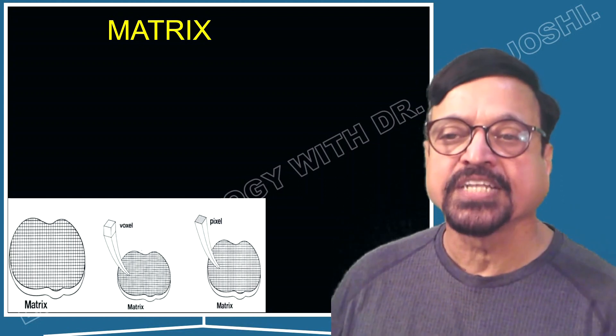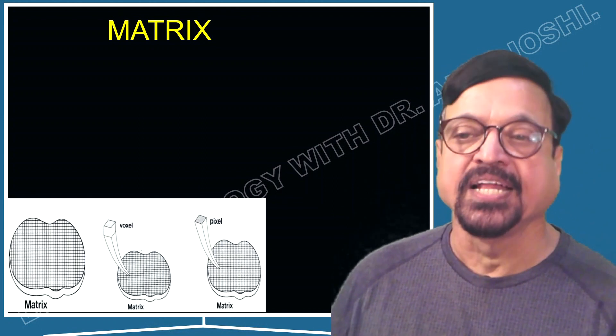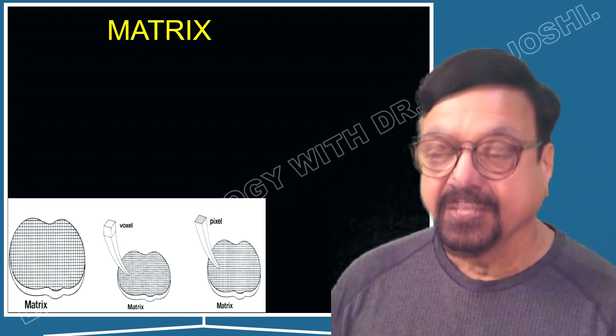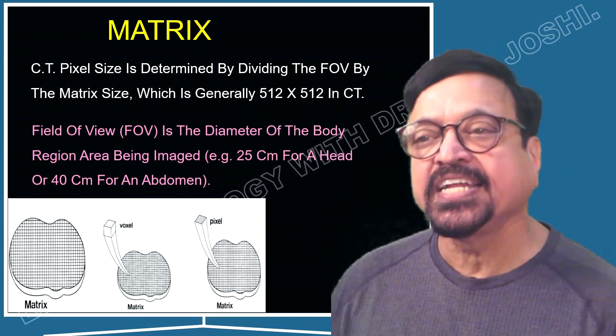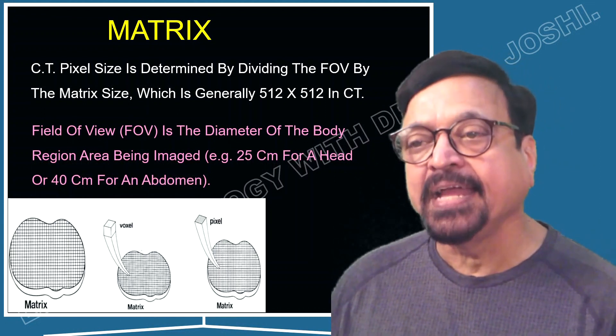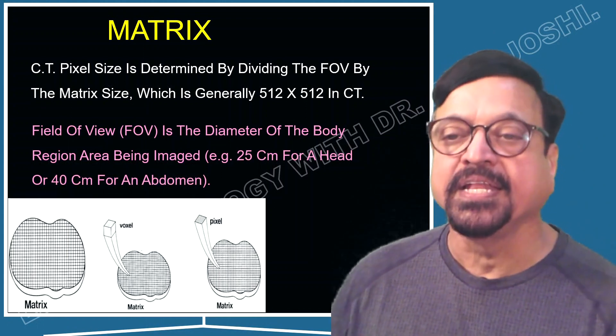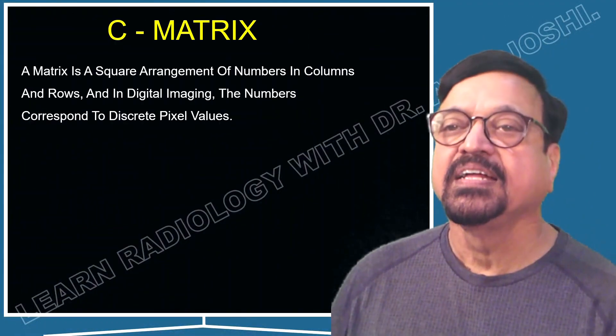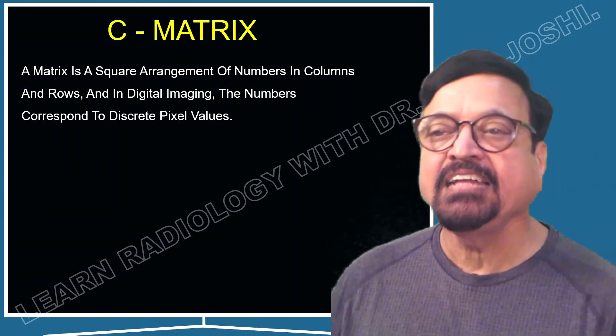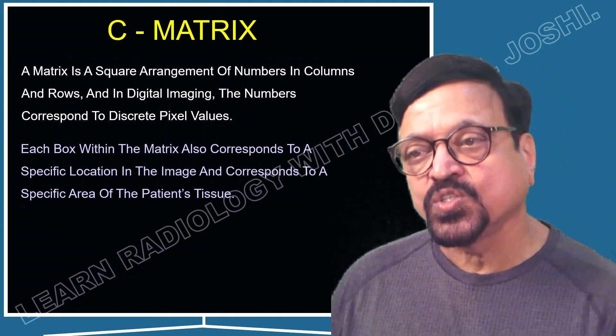Continuing with the matrix: looking at a cross-section of the body, you can see a matrix that is usually 512×512. This consists of voxels — remember, a voxel is a volume, it is three-dimensional. One element in the matrix is a voxel, while a pixel is the surface area of it — a two-dimensional thing. The CT pixel size is determined by dividing the FOV by the matrix size, which is generally 512×512. The FOV is the diameter of the body region being imaged — for example, 25 cm for the head or 40 cm for the abdomen. A matrix is a square arrangement of columns and rows.